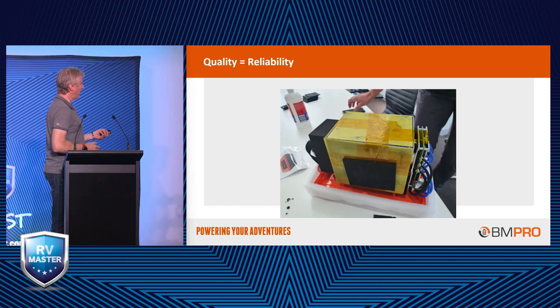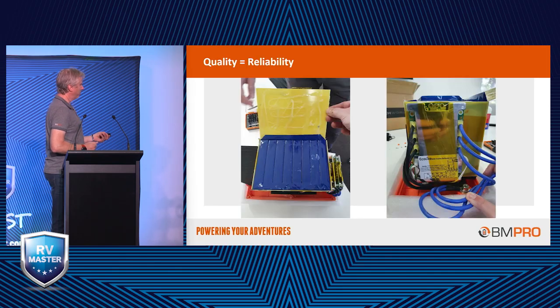I go on about this because I hate it from a safety perspective. It's just wrong - no temperature sensor in that one. Beautiful, so we've got 8 batteries in there with no temperature sensing. You're supposed to temp sense every cell in there to meet the standards of the BMS. There's not one temperature sensor there. This battery was opened on the desk in front of the Australian Battery Standards Society - they just freaked out.